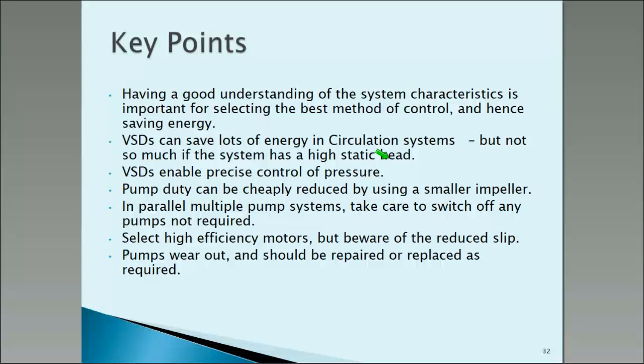Start by wanting to have a really good understanding of the system and how pumps work — from that you can select the best method of control. Variable speed drives are a really good way of saving energy, but not so good if you're trying to pump a lot of water uphill, because high static head reduces the saving potential. Variable speed drives can also give you very good control of pressure. Don't forget the trick of a smaller impeller. In multiple pump systems, it's so often the case that you can turn off two or three really big multi-hundred kilowatt motors and still have sufficient cooling water. High efficiency motors are obviously really good, but we do need to be a bit careful on systems which are mainly frictional. And pumps do wear out, so they should be repaired or replaced when needed.